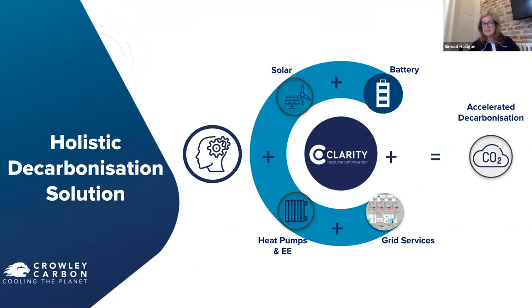Yep, they are. They are. The problem with them is that you're fueling them off electricity, which is at 12 or 14 cents, versus gas at 3 or 4 cents. So because they're about 99% efficient - more efficient than a gas-fired boiler - but the three-stage heat pump is 400% efficient. So the steam cost ultimately is on a par with gas, because of that 4-to-1 or 3-to-1 ratio between gas and electricity, but they are a simpler solution.